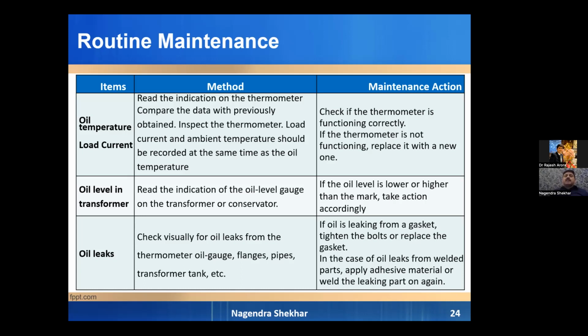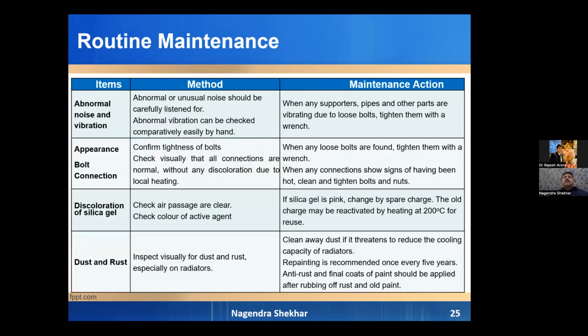We have to find out oil leakages. If we find any oil leakage from the radiator, gauge, bushing, or transformer tank, we have to ensure that these gaskets are tightened properly, and if they need replacement, we have to replace them. Abnormal noise and vibration: if it is noticed that the transformer is making an abnormal, unusual noise, we have to ensure whether any support is missing, or the sound is coming from the winding due to overloading or loose bolts. It is something which comes with experience. A new engineer cannot differentiate between normal and abnormal sound or the reasons for those abnormal sounds.